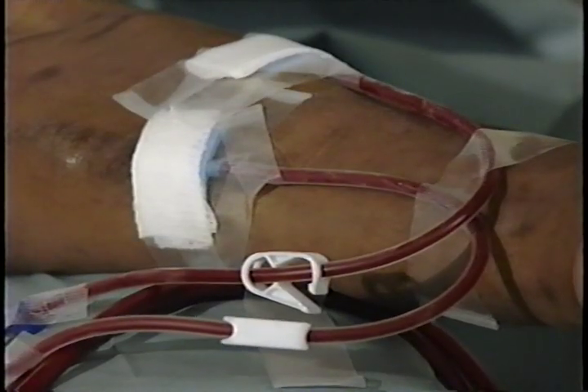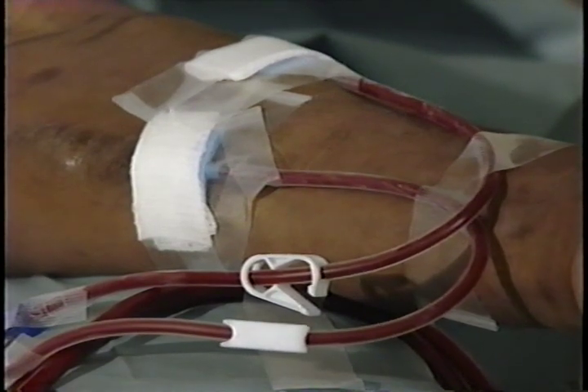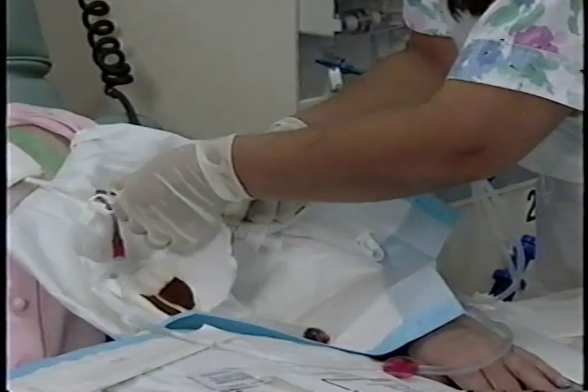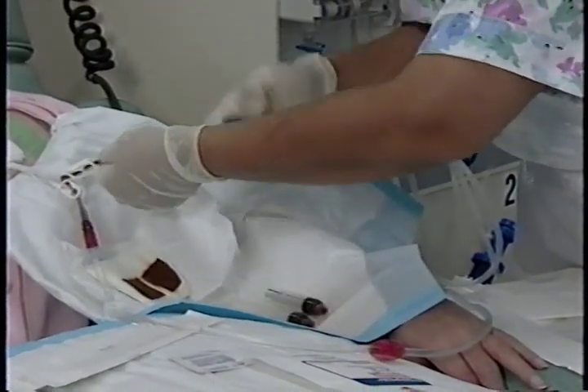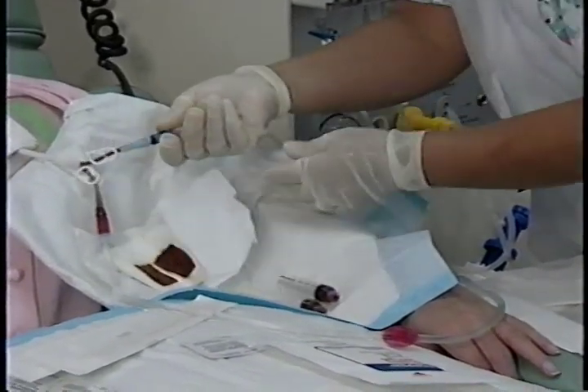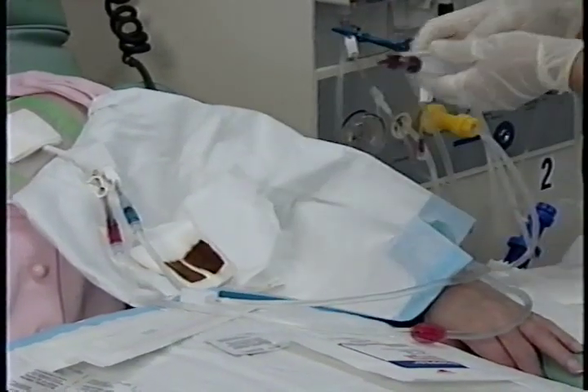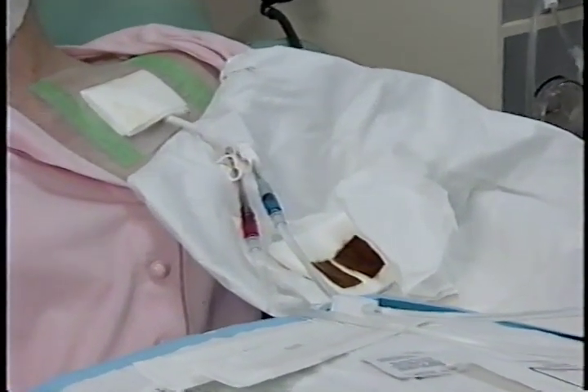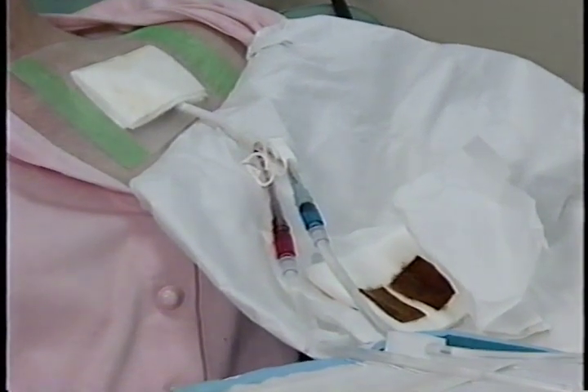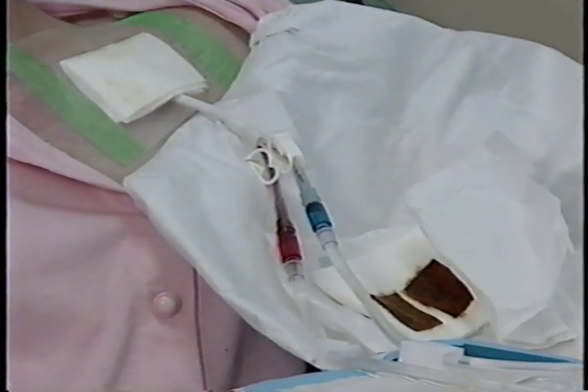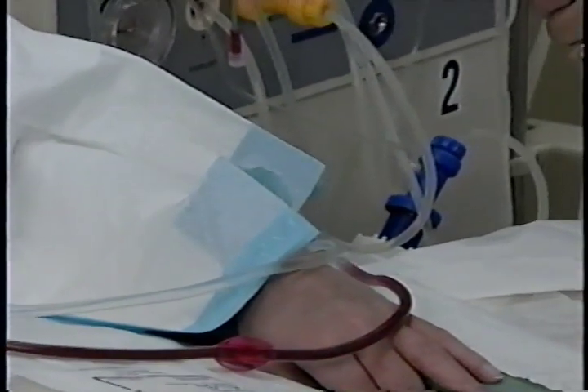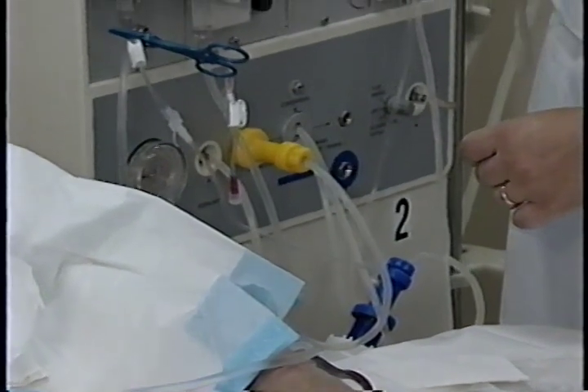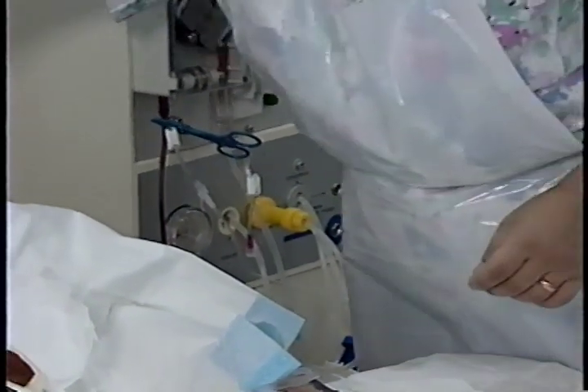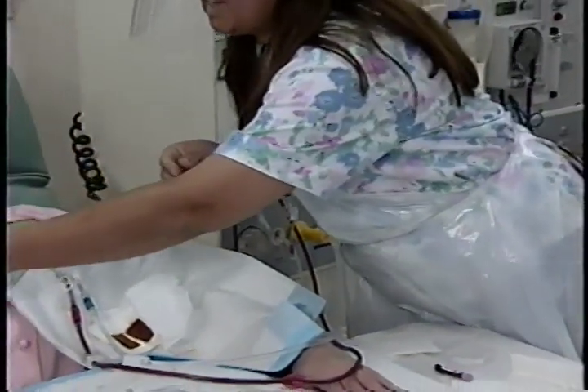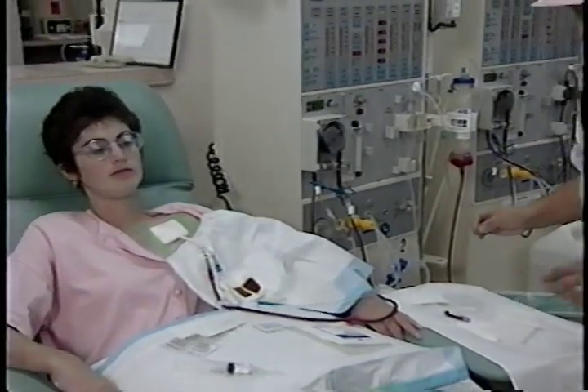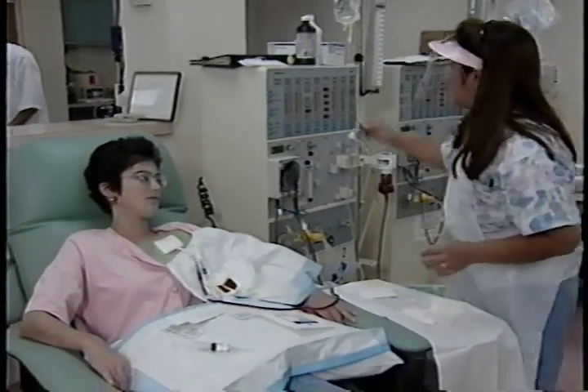In patients with fistulas or grafts, the patient's blood occasionally may appear darker than usual when recirculation is present. Blood routinely appears darker in patients with femoral or subclavian catheters because the catheters are inserted in veins, so the color of the blood is not always a good indicator of recirculation. Remember that dual lumen venous catheters are particularly susceptible to recirculation because the arterial and venous openings are so close together. It is not good practice to reverse the blood lines to improve blood flow. This can greatly increase recirculation and could affect the dialysis prescription. Recirculation is far more common than many clinicians realize and should be suspected whenever the Kt/V or URR results are lower than expected for the prescribed dialysis.